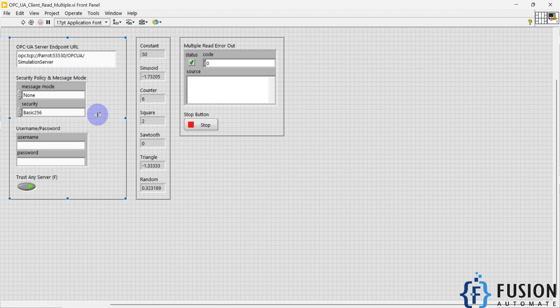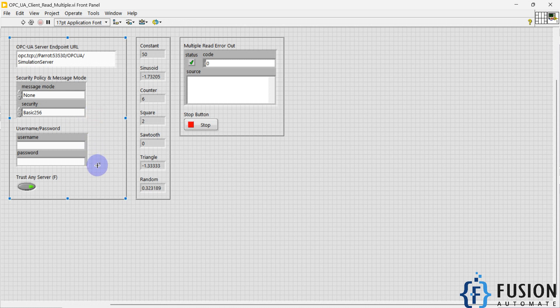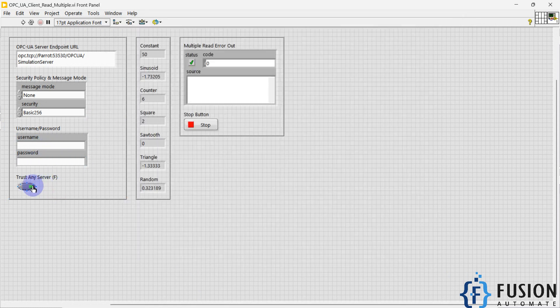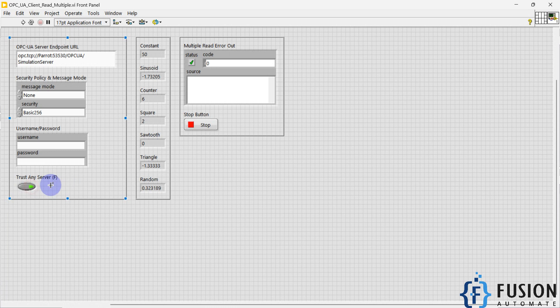After pasting the endpoint URL, you have to set your security policy and message mode. For me, the message mode is None and the security policy is Basic 256. If you have a username and password to connect to your OPC UA server, specify them here. If you want to trust any server, you can turn on that switch — it's off by default.